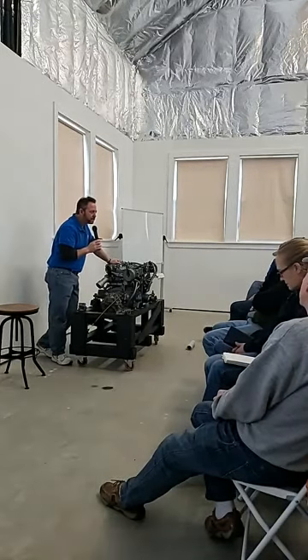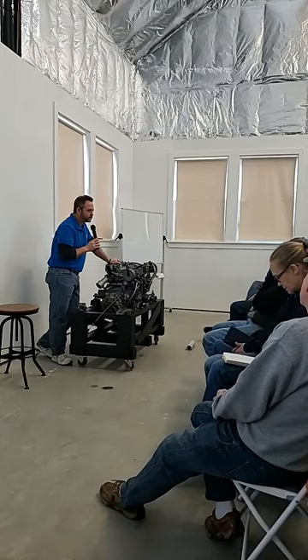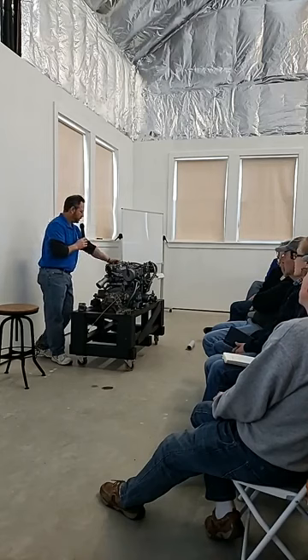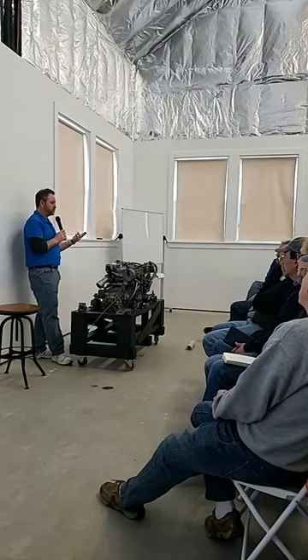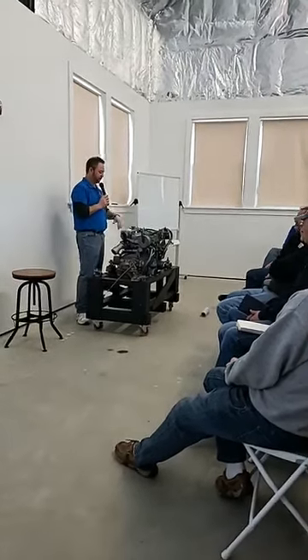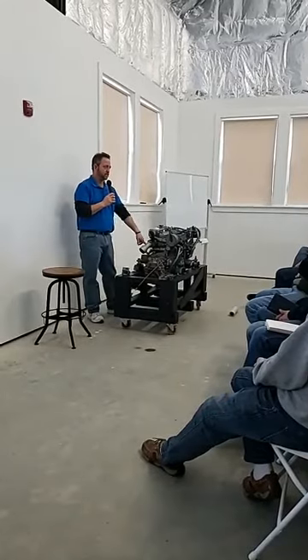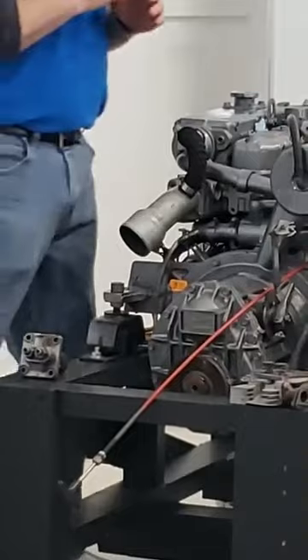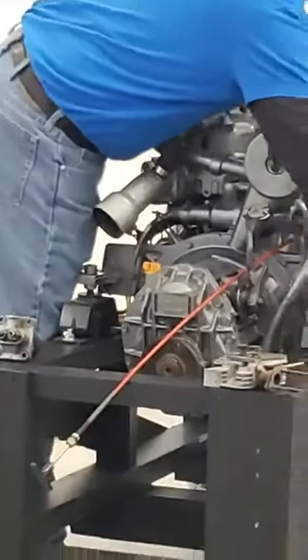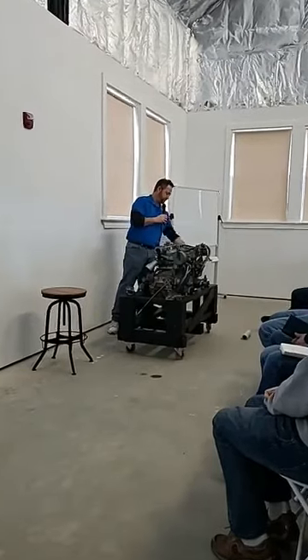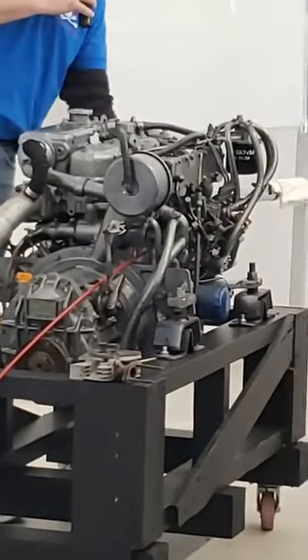When changing the antifreeze, where's the drain on the JH, the 4 JHs? The JHs typically have two or three drains, actually three. There's one on the back corner of the exhaust manifold, and then one on the side of the block, between the manifold and the circulation valve. There's a little drain in the front there.